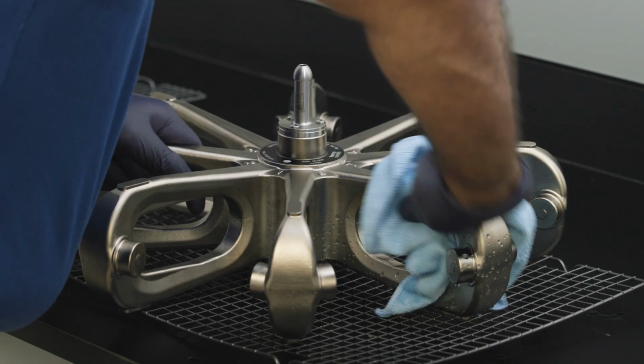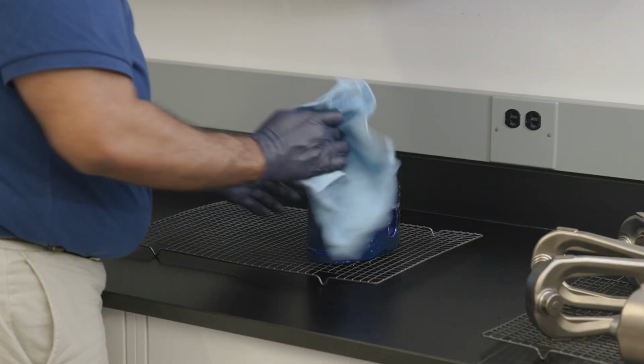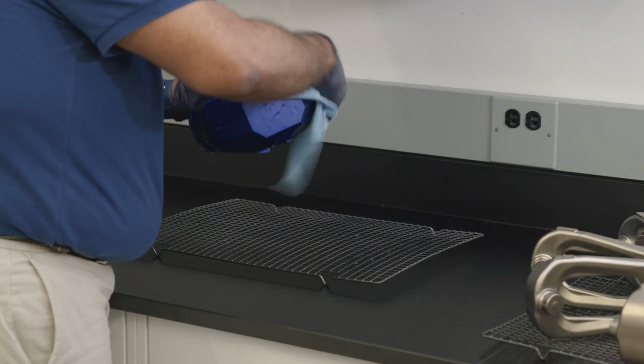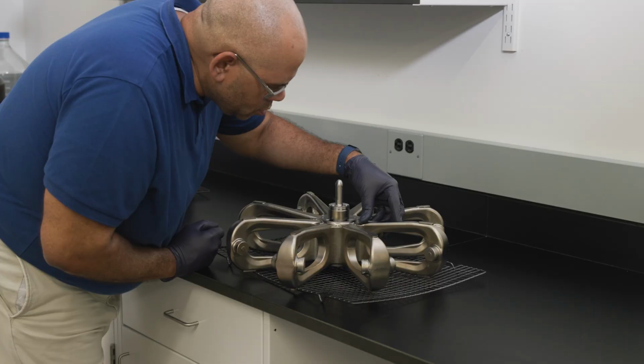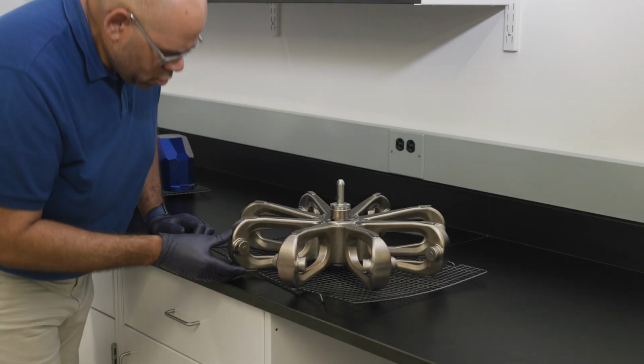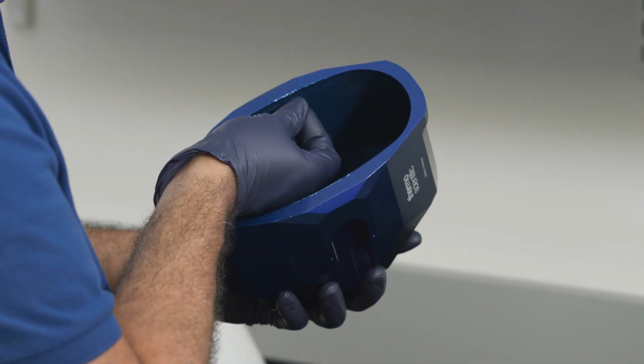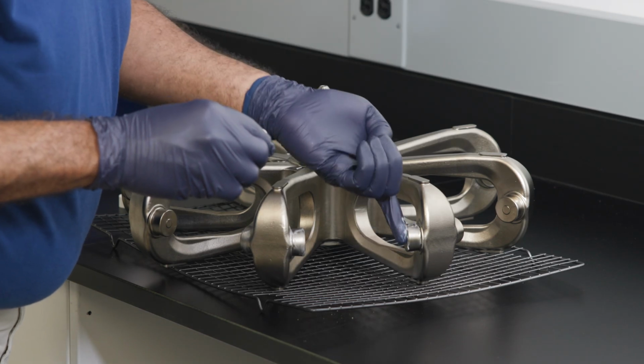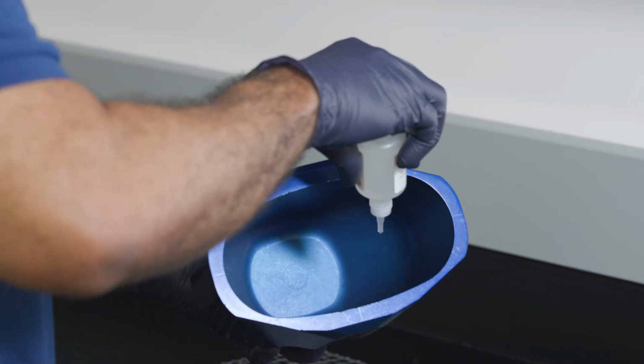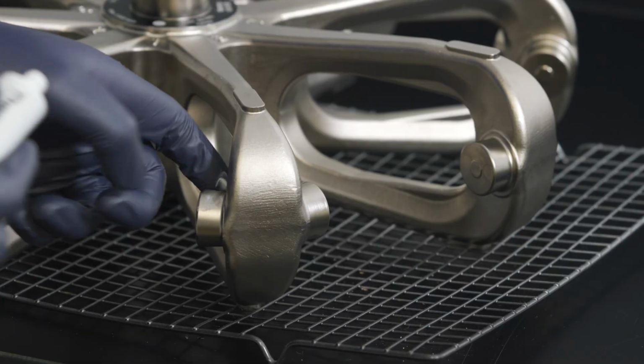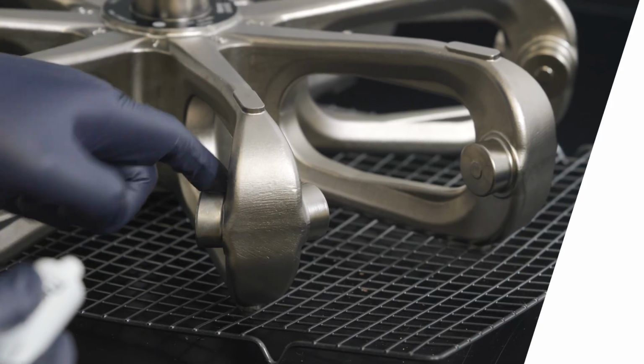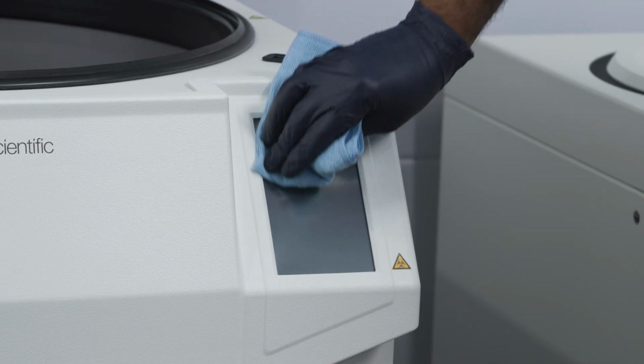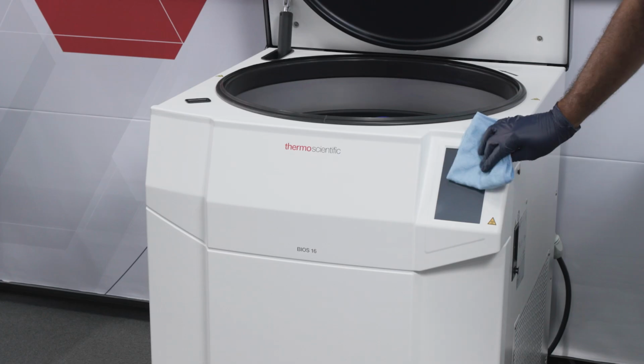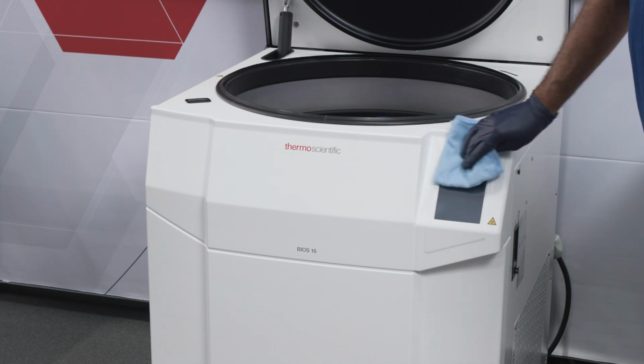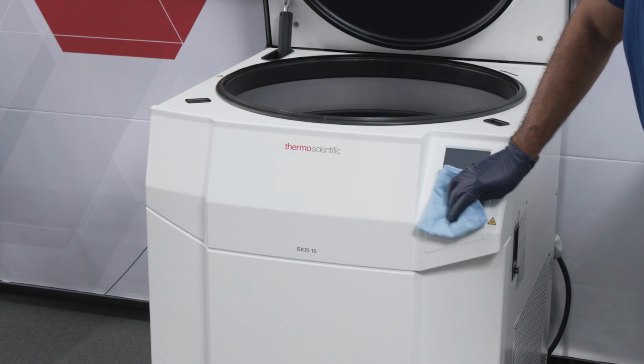Dry all components after cleaning with a cloth or in a warm air cabinet at a maximum temperature of 50 degrees Celsius. Then, inspect the rotor and accessories for signs of damage. After cleaning, treat the aluminum parts and their cavities with corrosion protection oil, and treat the bolts of the swing-out rotor with bolt grease. Next, pull out the power supply plug. Clean the touchscreen using a dry microfiber cloth and, if necessary, moisten the microfiber cloth and wipe the touchscreen again.